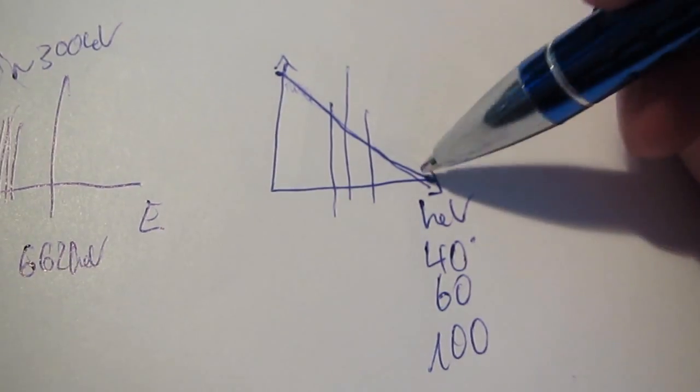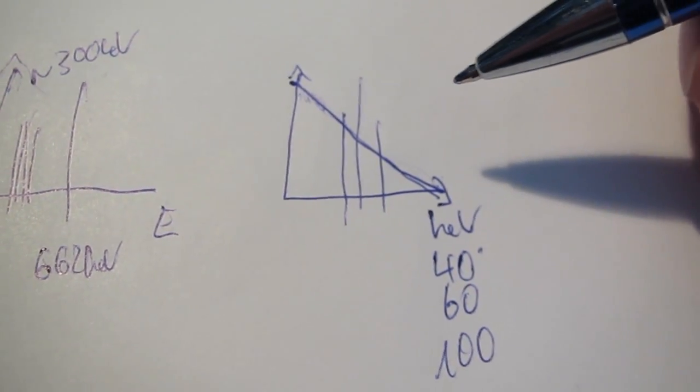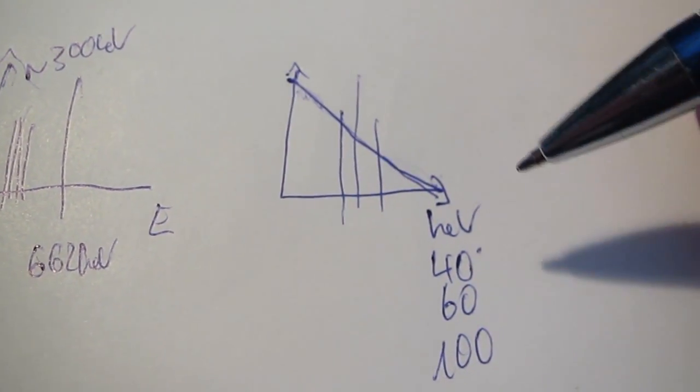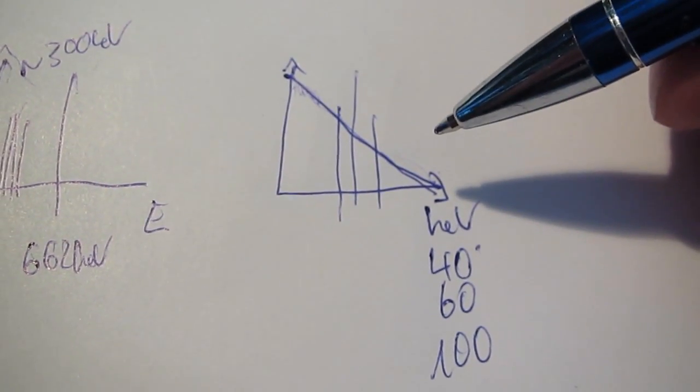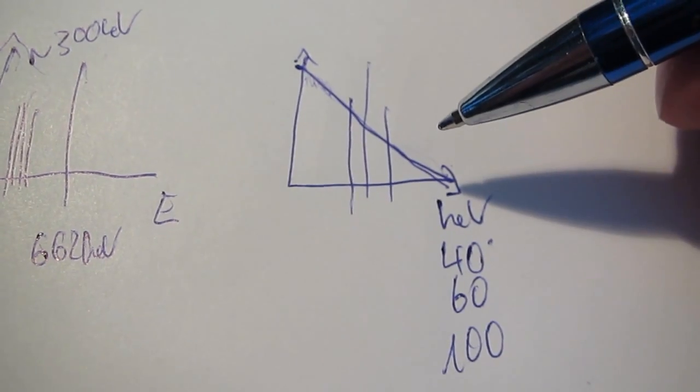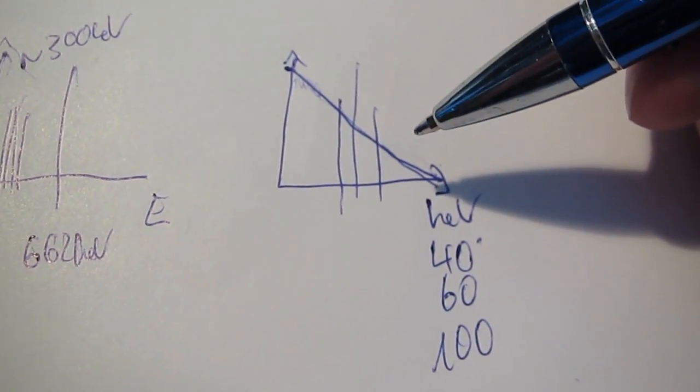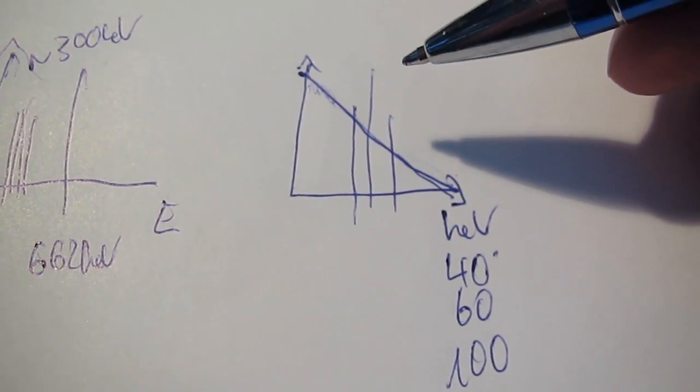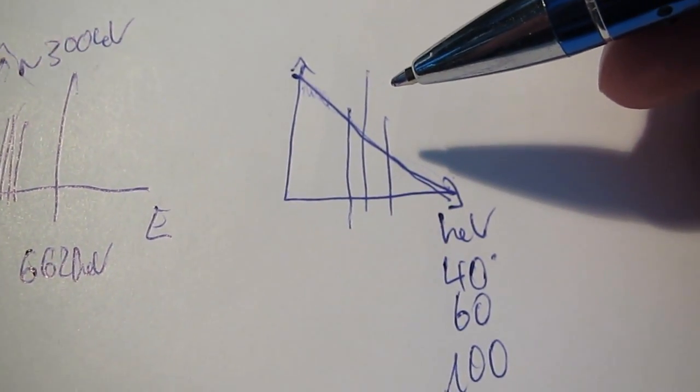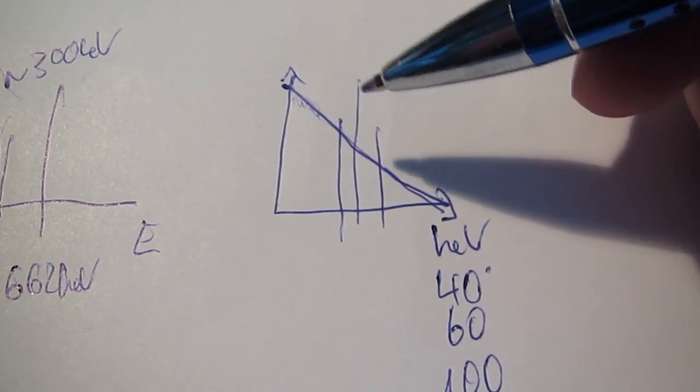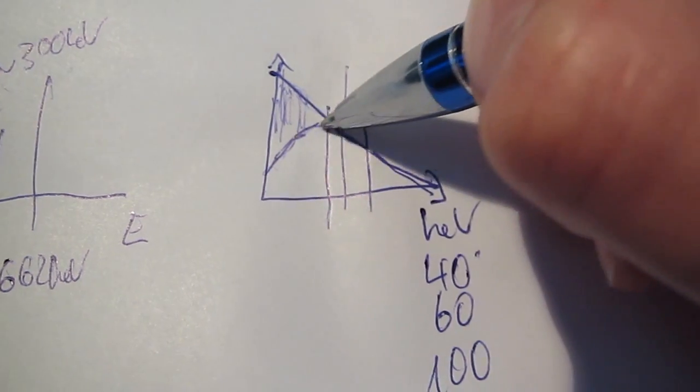But this linear fashion photon energy flux pretty much is just a theoretical spectrum, because there's actually filtering or shielding happening within the tube material itself. You know, the x-ray tube is made out of glass. It's a vacuum, but of course it contains something around it, that is glass typically. The window is made of glass in our tubes. The anode material itself shields some x-rays, so you pretty much filter out most of these very low energy x-rays. So your real spectrum actually looks like this pretty much. So you have very few, or pretty much it starts here actually.